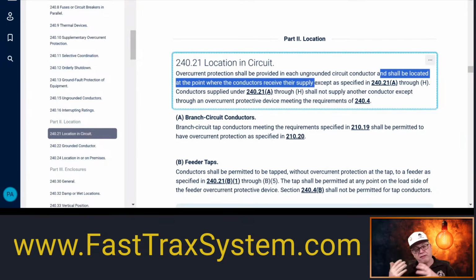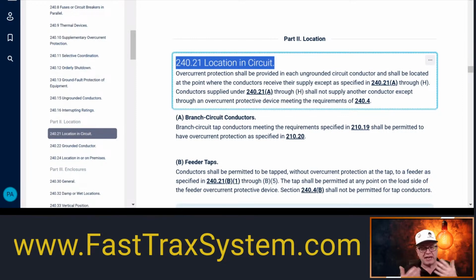So typically, what we do is we have conductors, and you hook them to overcurrent devices, and they're being protected. So these rules are allowances that say, you know what, I can tap onto a certain conductor, and I don't have to worry about the overcurrent protection device being located where that tap is. And the reason we call the secondary conductors for the transformer the secondary conductors is because they are also connecting onto somewhere that does not have overcurrent protection at the point where those connections are made, right? So this is all this is talking about, the location of where that overcurrent protection has to be. And of course, the general rule is you protect the conductor at the point where the conductor receives its power, which is what we normally would do when we take conductors and hook them onto breakers. They're being protected, and that's why we size breakers the way we do.